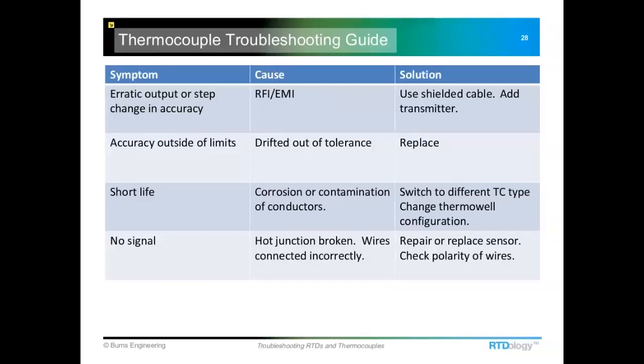Thermocouples are even more susceptible to RFI and EMI than RTDs. We're only measuring a millivolt signal, and it doesn't take much interference to cause it to be very erratic or cause a step change in temperature. Ways around this include using a good shielded cable grounded at the signal conditioner end with the shield open at the temperature probe end so it can drain noise away. Another solution is to put a transmitter at the temperature measurement location and run a current or voltage signal back to your control system — those are much more resistant to RFI/EMI interference.